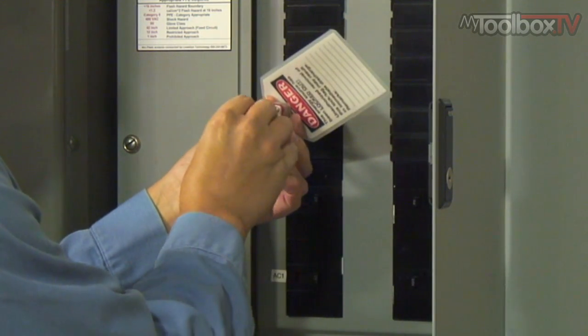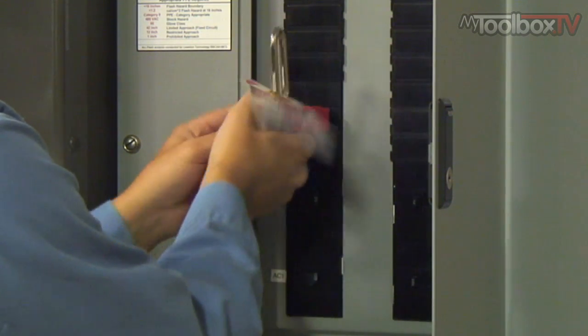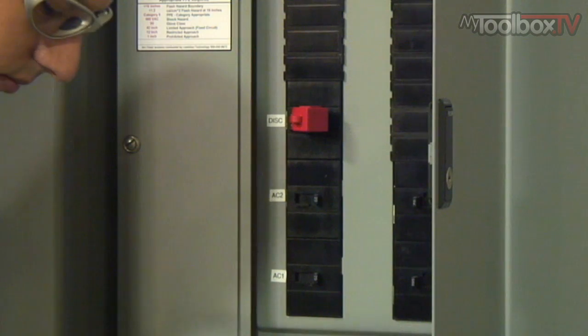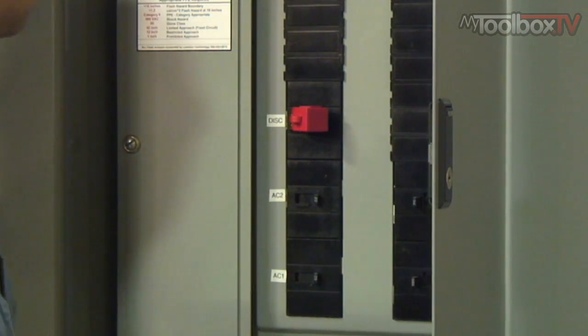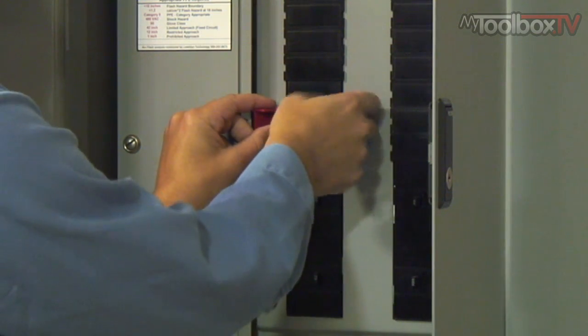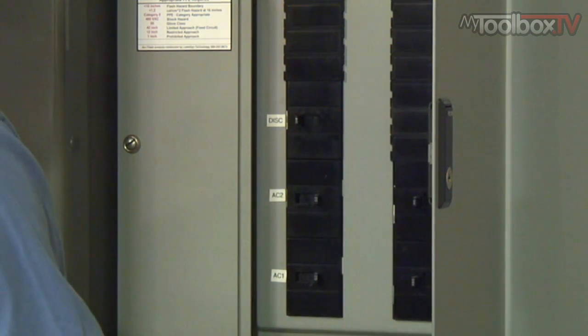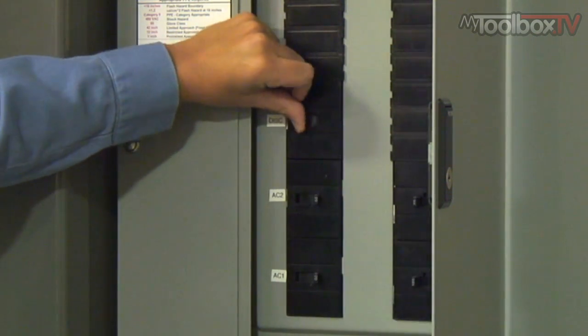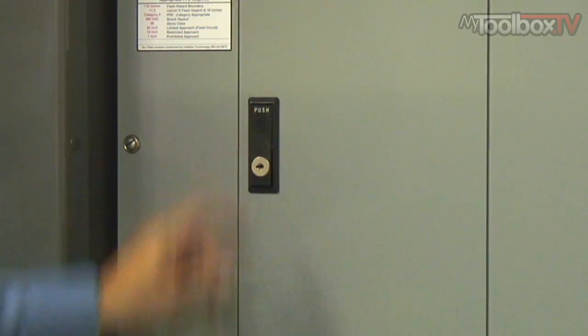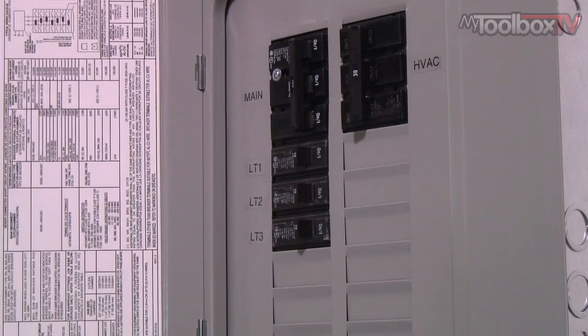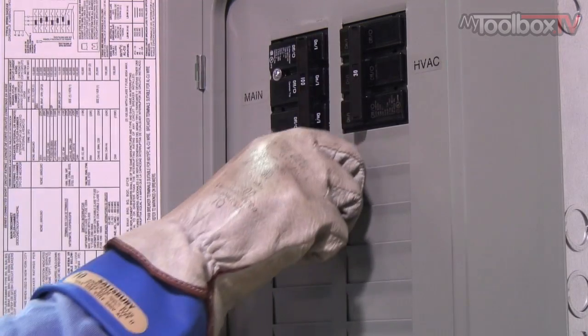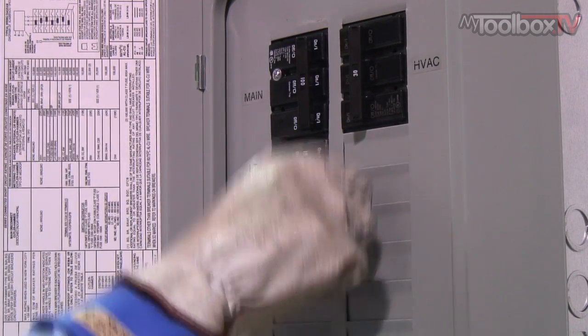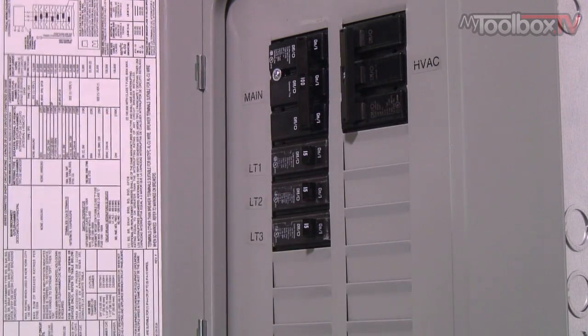We remove the lockout tagout device. And once again, you follow your company's procedures and policies on getting this particular procedure done. We'll turn on that circuit breaker, the upstream circuit breaker first. The panel is turned off. Now we're turning on the loads in the main breaker for that panel. And our work is done.